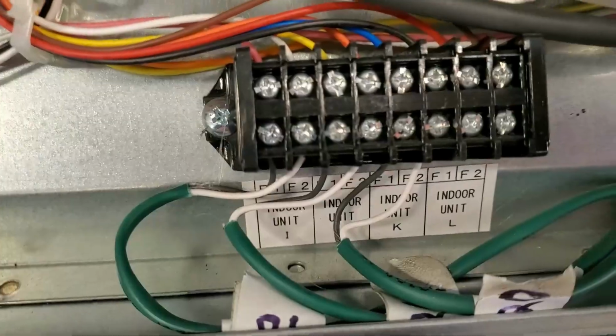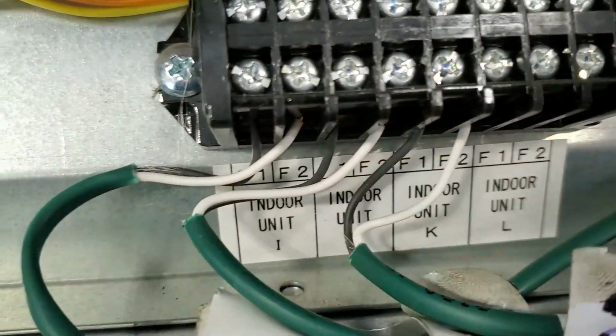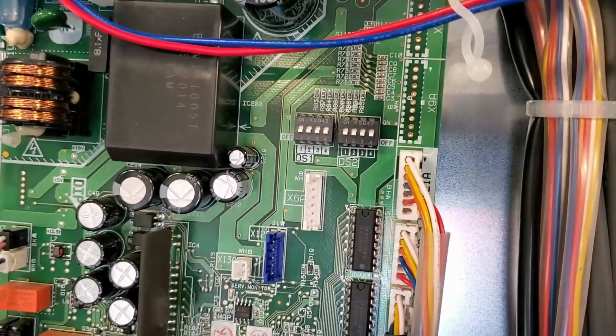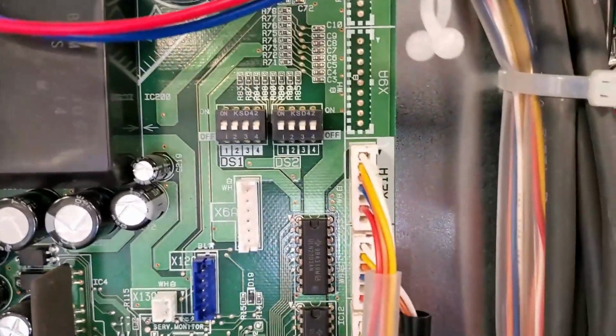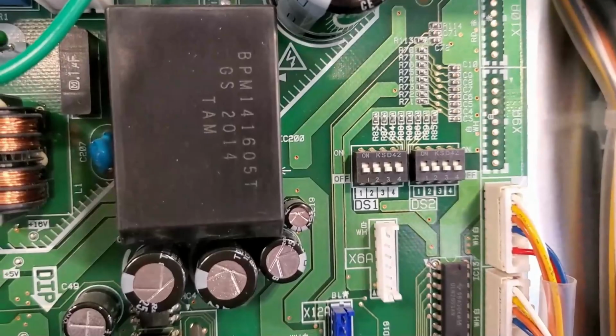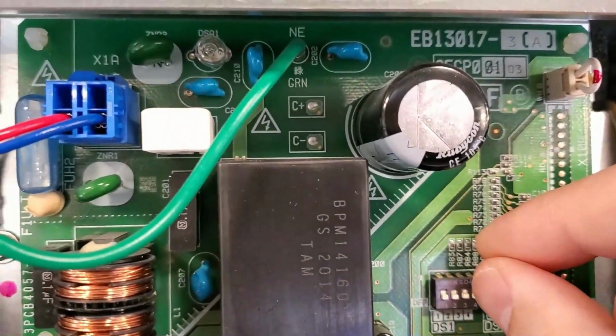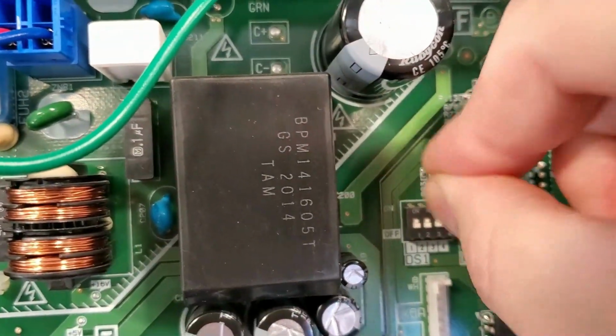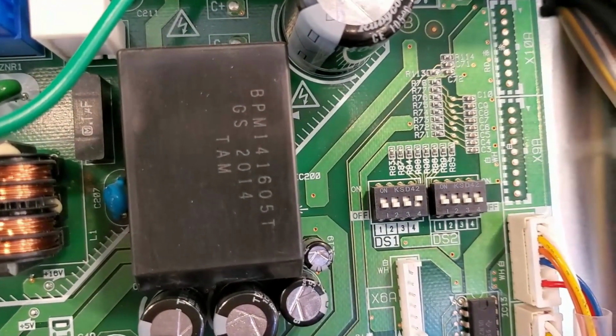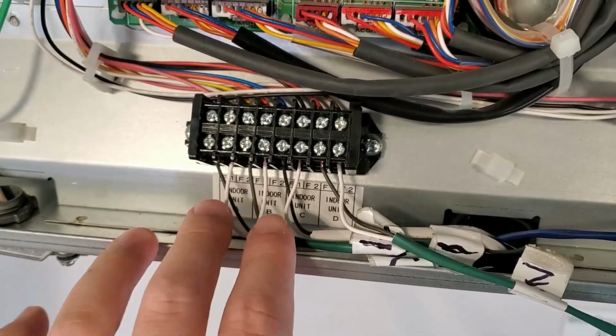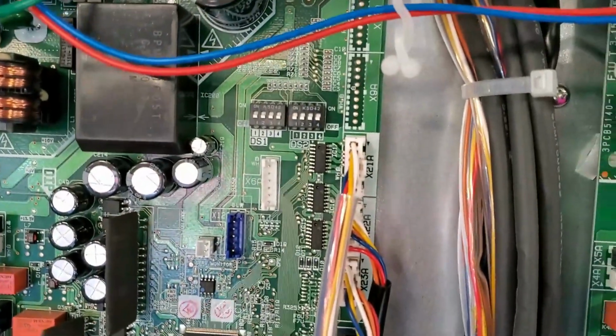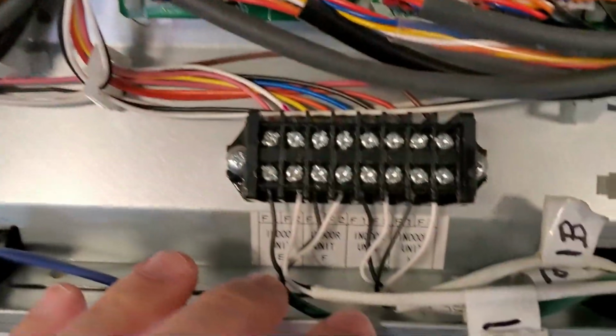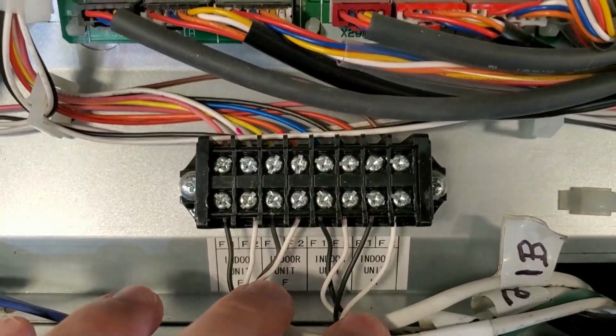You need to make sure before you power up the branch boxes, because those are next. After you power up all the indoors, you power up the branch boxes. But before you power up the branch boxes, you need to make sure that you properly set all the dip switches on each of the branch boxes for the system that you are going through and powering up. And the reason is because you need to make sure you disable the ports not being used, twin the sets of ports that are twinned, and you need to make sure you verify that the proper switches are turned on that disable ghost ports on your 6 and 10 port boxes.